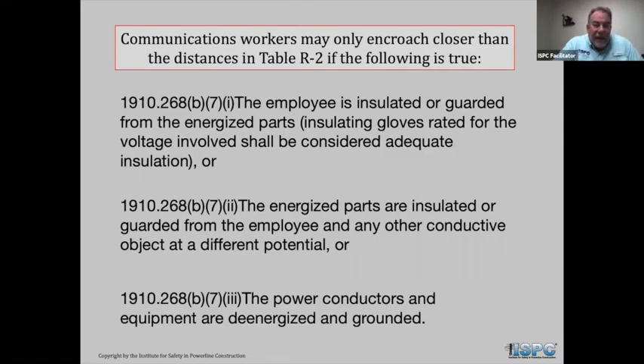All right. Communication workers may only encroach closer than the distances if the employee is insulated or guarded from the energized parts. Insulating gloves rated for the voltage involved shall be considered adequate insulation, or the energized parts are insulated, or are guarded from the employee and any other conductive object at a different potential. So we're talking about some covering.